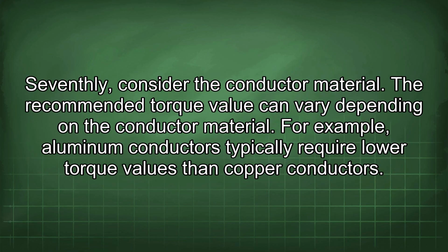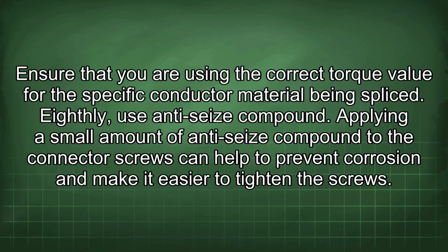Seventhly, consider the conductor material. The recommended torque value can vary depending on the conductor material. For example, aluminum conductors typically require lower torque values than copper conductors. Ensure that you are using the correct torque value for the specific conductor material being spliced.